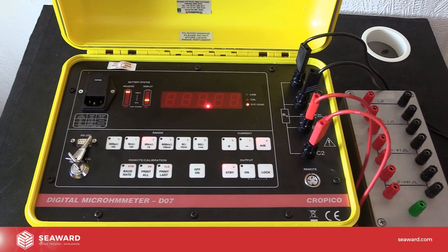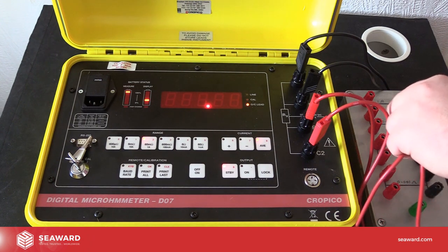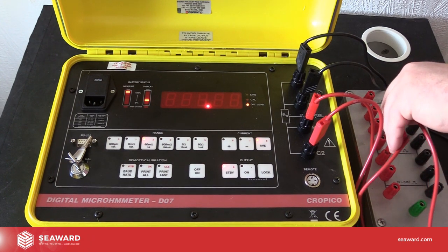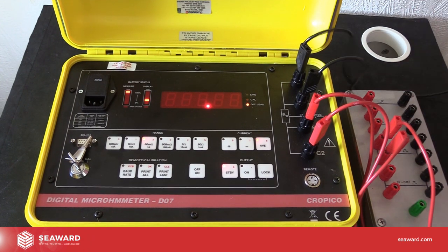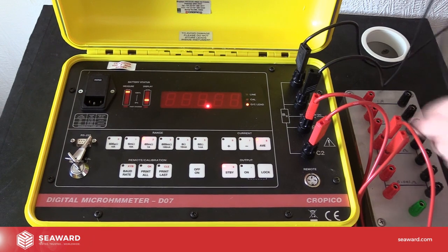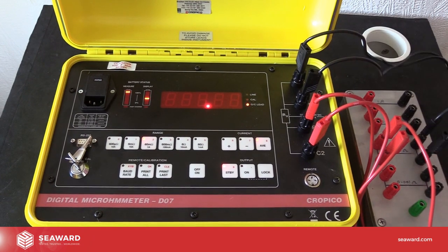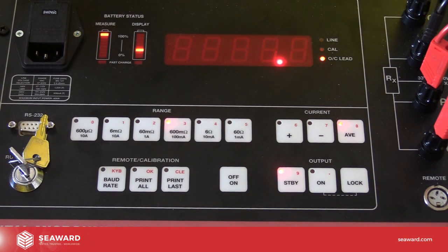In the case of our resistance box, they're color coded, but quite simply we need to keep the red leads on one side of the resistance we want to measure and take the black leads to the other side of the resistance we want to measure. So let's connect this up. And we're ready to begin the measuring process. Okay, so we now have the D07 connected to the measurement device. We can start to set the instrument up to take measurements.